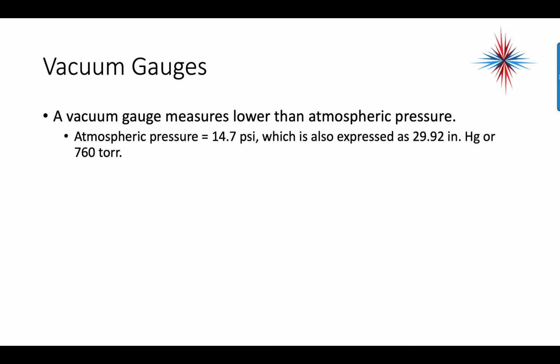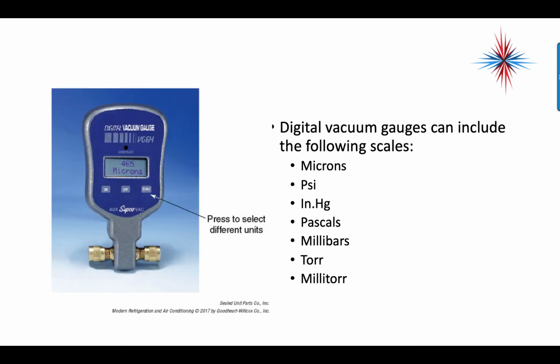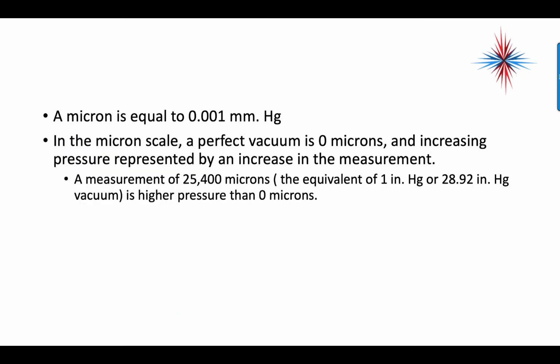A vacuum gauge measures lower than atmospheric pressure. Atmospheric pressure is at 14.7 psi, which is 29.92 inches mercury, or 760 torr. Digital vacuum gauges can include the following scales: microns, psi, inches mercury, pascals, millibars, torr, or millitorr. Okay, and you can actually press the scale to select the different units. Most often now with vacuum, we are using microns. A micron is equal to 0.001 millimeter of mercury. Hg is mercury.